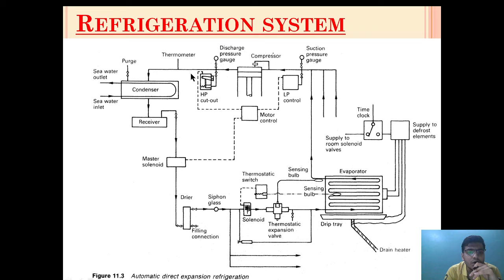The high pressure refrigerant gas will be cooled in the condenser by seawater or fresh water. As it is cooled, the gas form of refrigerant at high pressure will be collected in a receiver unit in liquid form. From there, the liquid refrigerant will flow past through a master solenoid and then through a dryer, to eliminate any mist particles, water particles, or any carryover of oil particles from the compressor.